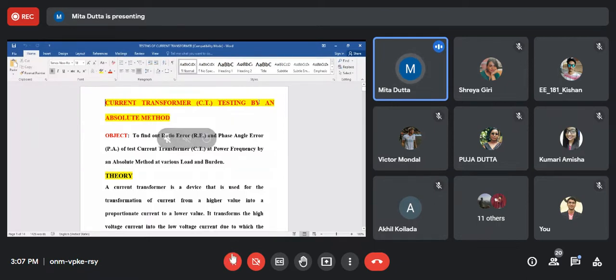I am asking something. So when we are going to connect a current transformer to measure current in a high voltage, high current circuit, we will connect the primary winding in series with the line, and the secondary winding is connected across, and across the secondary terminals of the CT we will connect the measuring device or measuring instrument, and in the case of a CT, the measuring instrument is nothing but an AC ammeter.